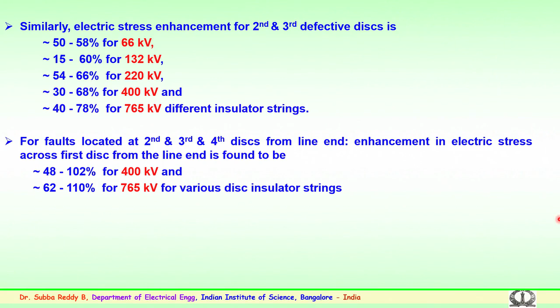So, what happens in the case of faults where three insulators are shorted or faulty in the string from the line end? You can see the increase will be more than 100% for 400 kV and 765 kV disc insulators. This table gives the entire information about the percentage of electric stress across the first disc. Here the first disc assumed is the good one, the second, third and fourth are treated as faulty, and simulations have been conducted and stress calculations have been made for various discs.